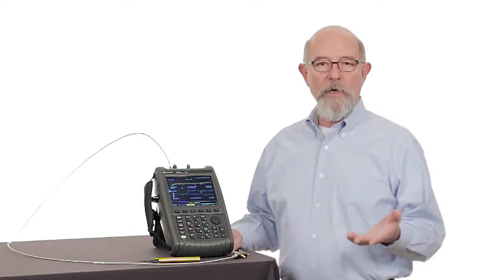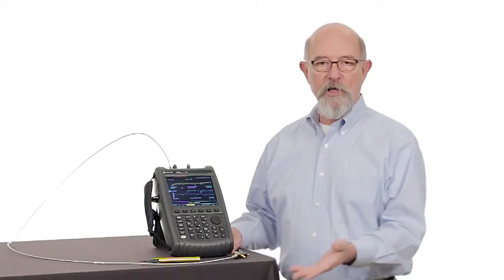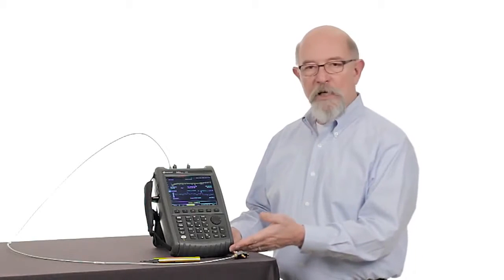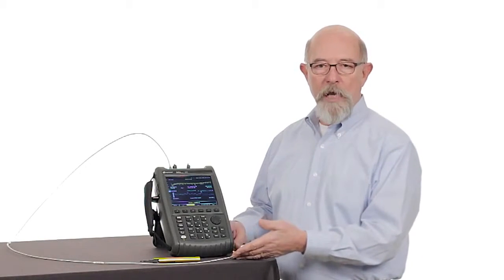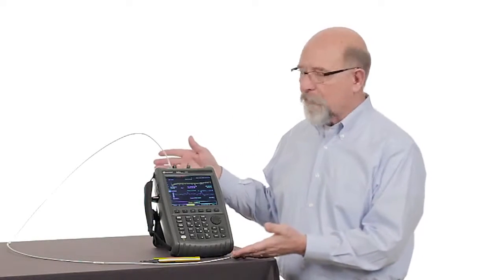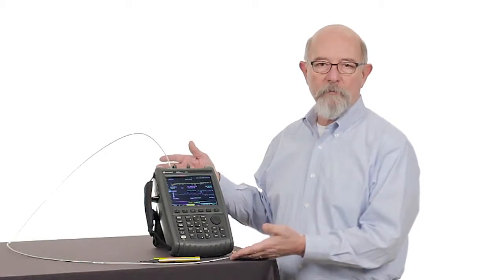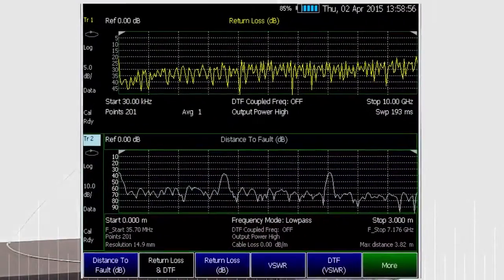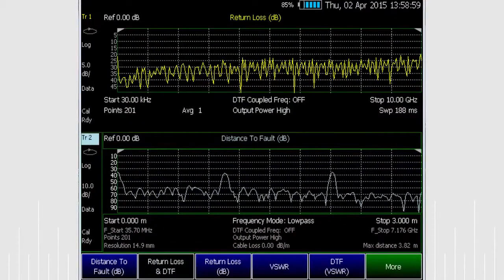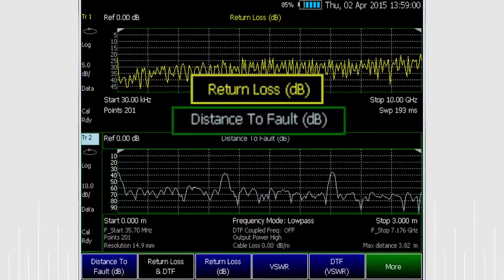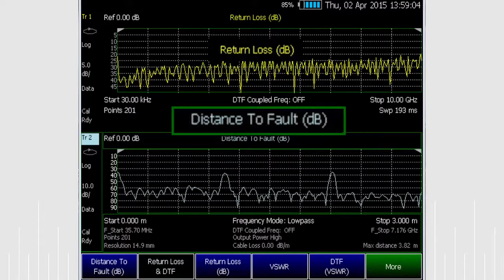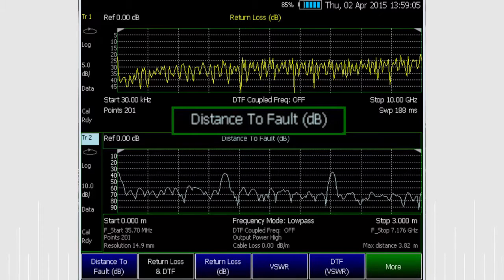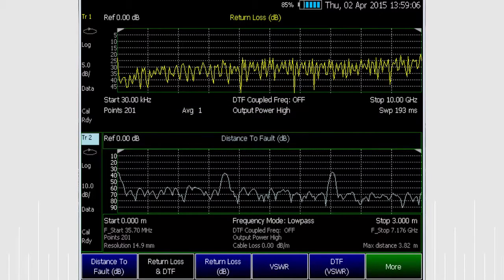What I'm showing here is a simple set of cables, connectors, and a 50-ohm load as an example of a transmission line. The first step in analyzing the cable's performance is to line sweep. We'll be looking at return loss and distance to fault.